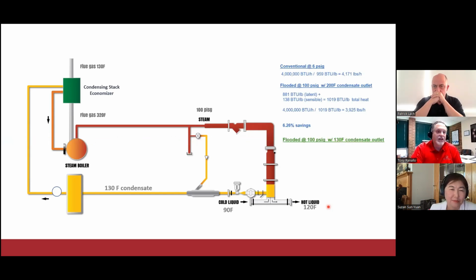If we look at this as a flooded heat exchanger, where we may want to drop the condensate outlet temperature to 130 degrees, which we can do if our liquid temperature, as you see down here, may be in the realm of low temperature like we would use with, say, condensing boilers, right? We can now increase our amount of sensible heat recovered, and all of a sudden, we can use 9.53% less steam.